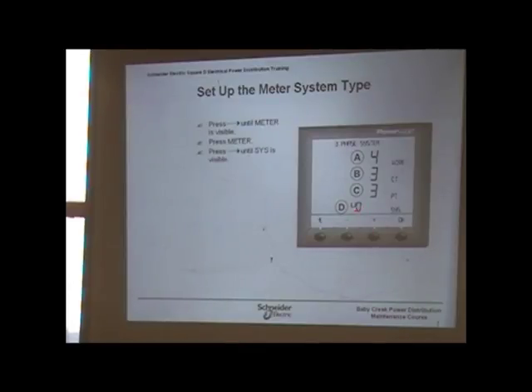We used to have to know these by heart, or pull the book out each time, because it could be a 3-wire system with 3 CTs and 3 PTs, or a 4-wire system with 2 CTs and 3 PTs, or it could calculate B phase current using the A phase and C phase CTs. And the same thing with the PTs, or it could be 3 CTs with 2 PTs, and so forth and so on. So it was crazy.